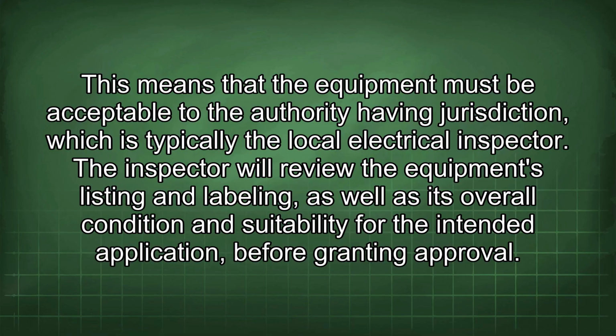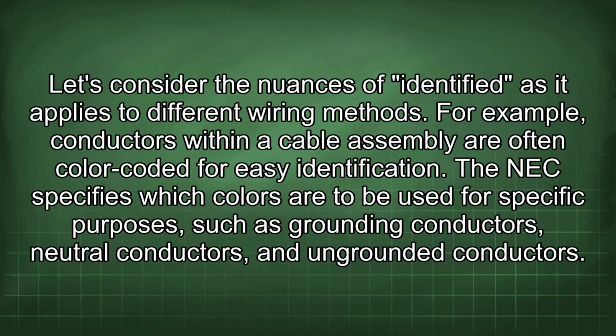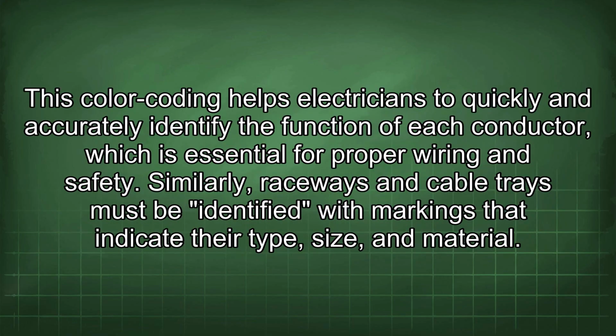This means that the equipment must be acceptable to the authority having jurisdiction, which is typically the local electrical inspector. The inspector will review the equipment's listing and labeling, as well as its overall condition and suitability for the intended application, before granting approval. Let's consider the nuances of identified as it applies to different wiring methods. For example, conductors within a cable assembly are often color-coded for easy identification. The NEC specifies which colors are to be used for specific purposes, such as grounding conductors, neutral conductors, and ungrounded conductors. This color coding helps electricians to quickly and accurately identify the function of each conductor, which is essential for proper wiring and safety.